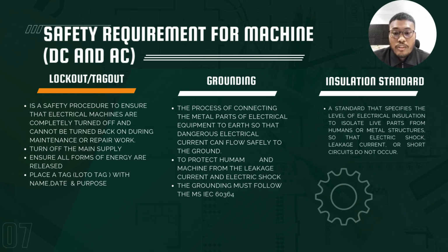Second, grounding: this is the process of connecting the metal parts of electrical equipment to earth so that dangerous electrical current can flow safely to the ground. This method protects humans and the machine from leakage current and electrical shock, and the wiring grounding must follow MS IEC 60364.